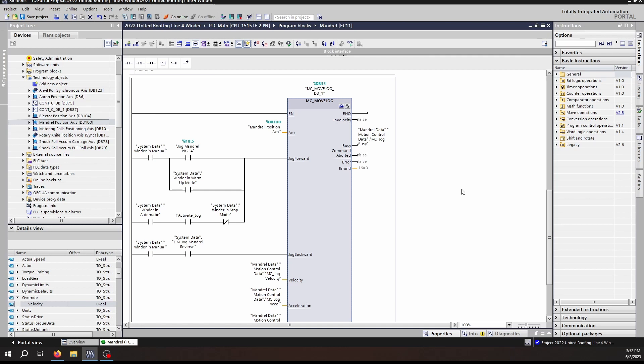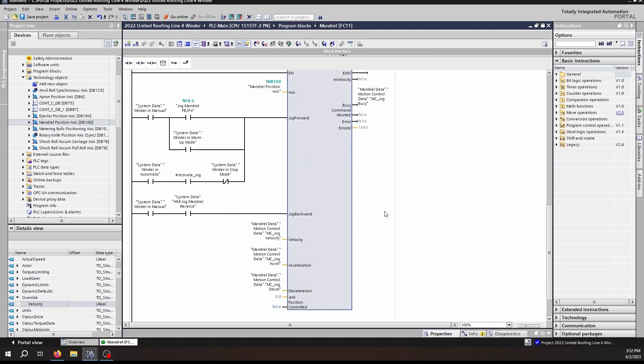It operates to where all of the inputs of this block are updated on demand. That means if you change the velocity input while you are running this block, then the velocity will actually change. This actually means that you do not have to use the override velocity in order to change the velocity during a move. You can change the MC Jog velocity as shown here directly while it is moving, and it will change the velocity. Functionally, that is about the only difference between it and the MC Move Velocity.